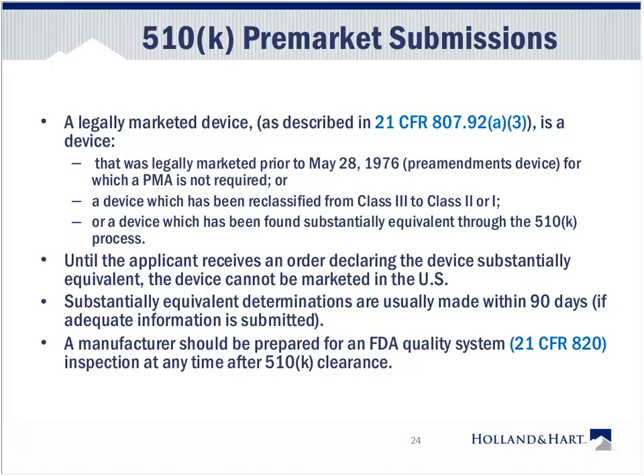Or a legally marketed device can be a device which has been reclassified from a Class 3 to a Class 2 or 1. And you think, well, how often would that happen? It's actually happened with a large number of devices in the new world of medical apps. Several medical apps, especially relating to telehealth and the transmission of health information for mobile uses, were originally classified or required Class 3 status. And they have since been reclassified by the FDA to a 2 or a 1, because we've become so standardized and we realize how good that process has become. So if something has gone through the rigors of a Class 3 clearance and is reclassified to a 2 or 1, it does not need a new approval basis from the FDA.